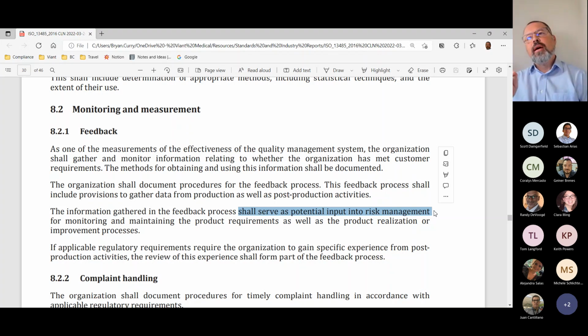But I think from a risk management perspective, when it talks about feedback, remember that part of the purpose of the ISO standard is to serve the OEMs as well as the contract manufacturers. So as I look at this feedback section, one way I'd apply this if I were an OEM is that I might get a lot of feedback from hospitals or surgeons about the performance of the device that is not necessarily a complaint, but might address user needs.